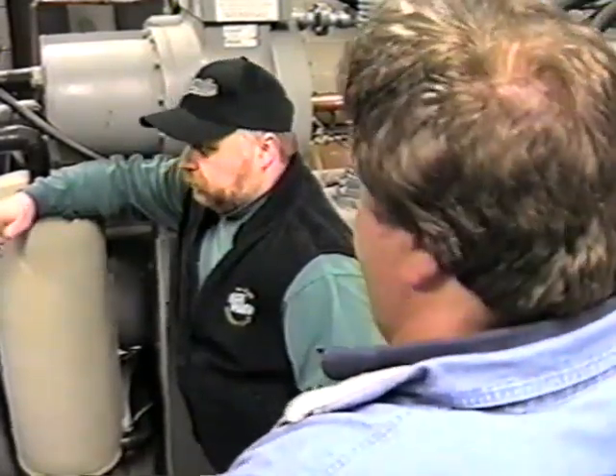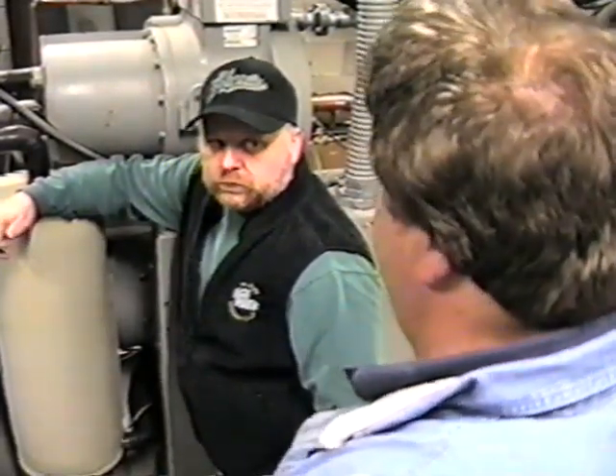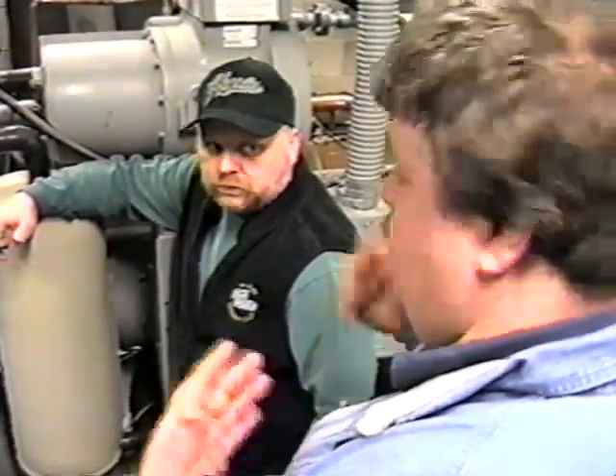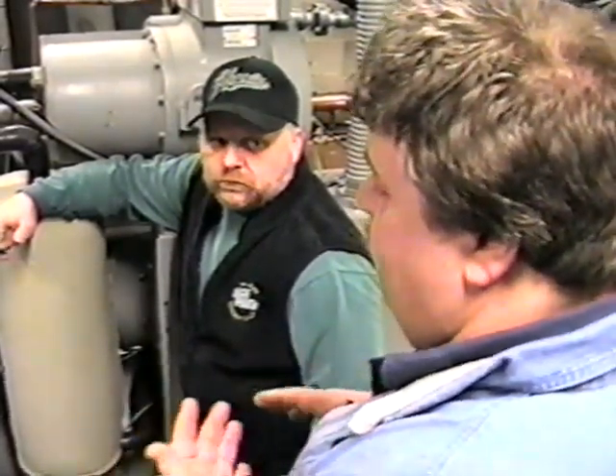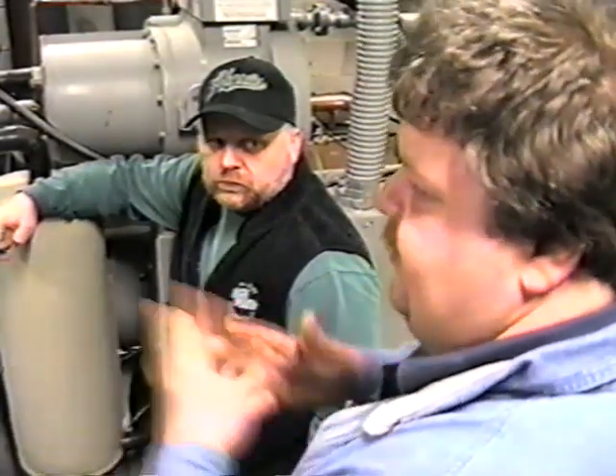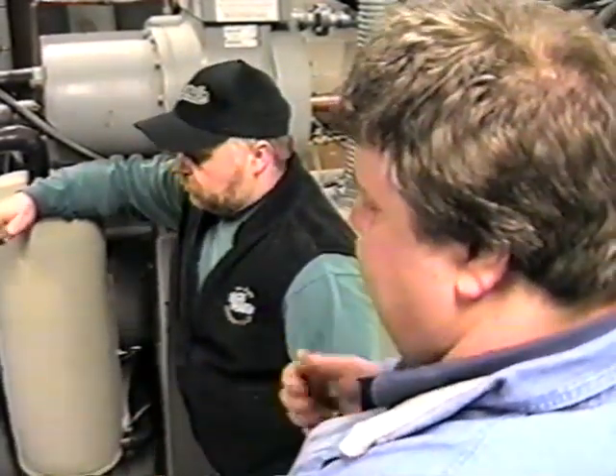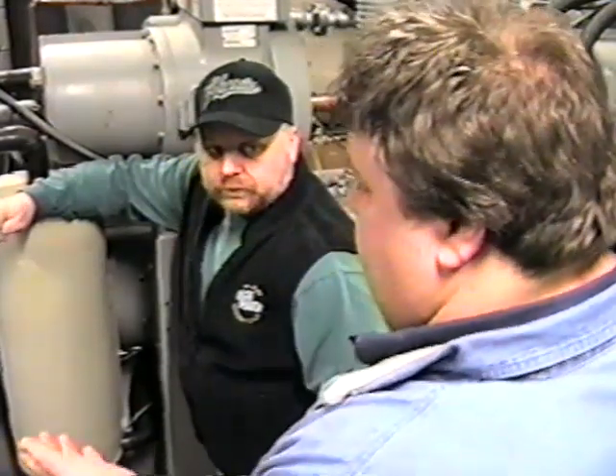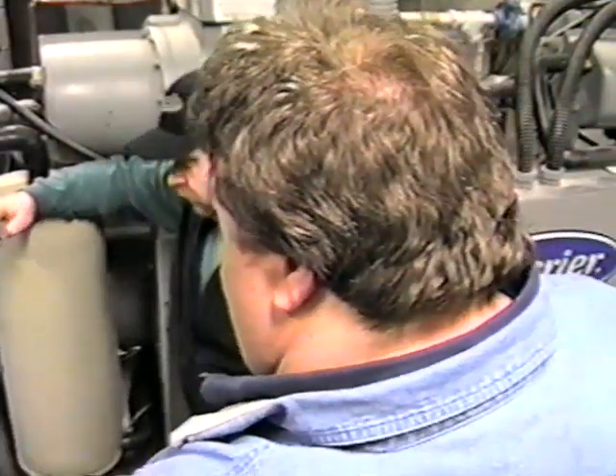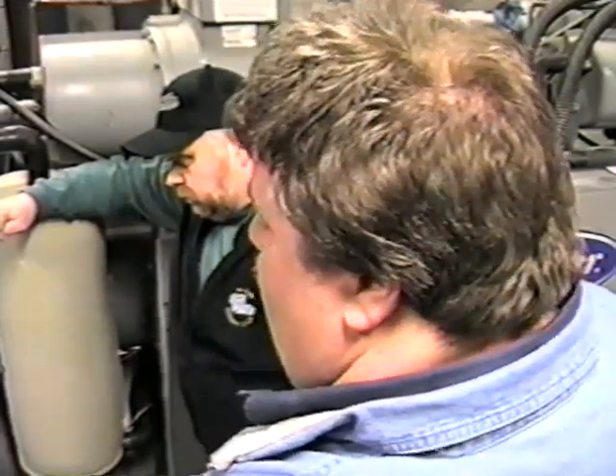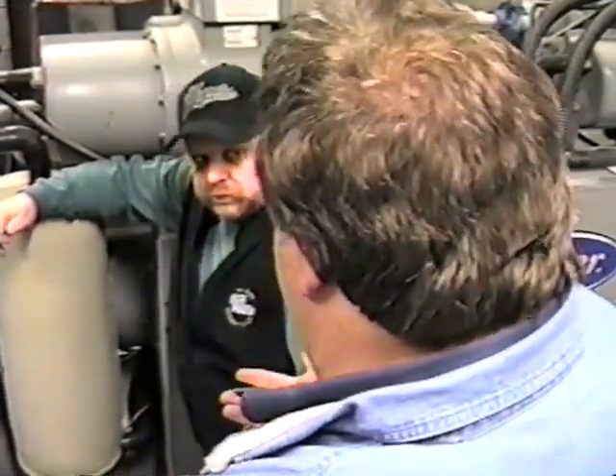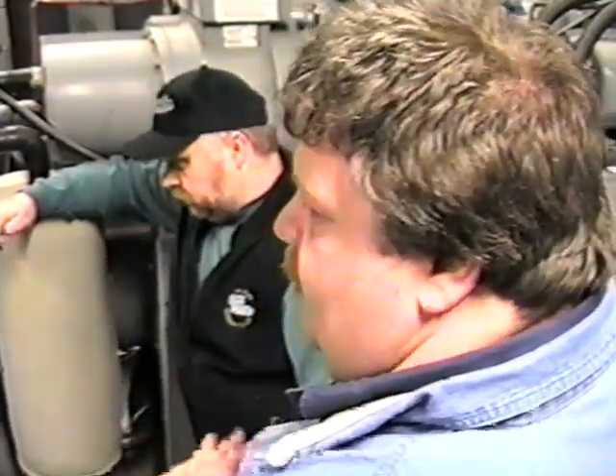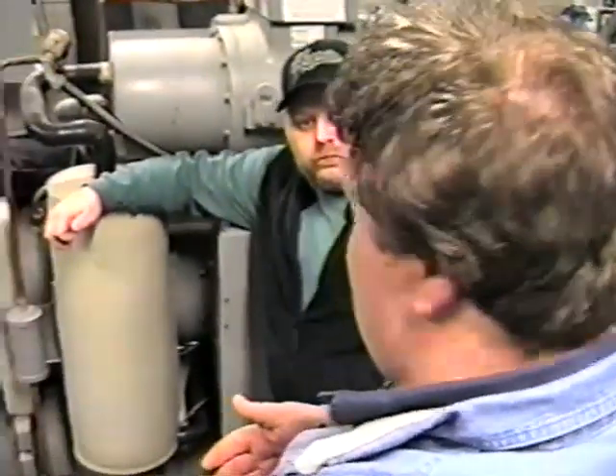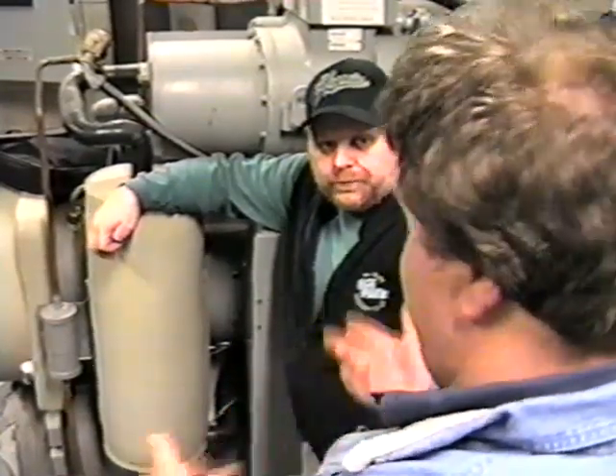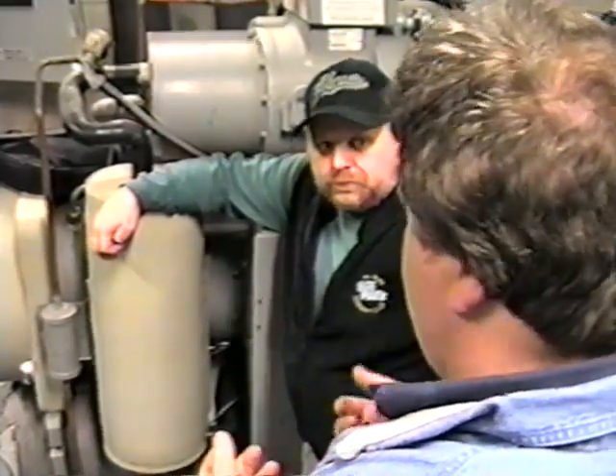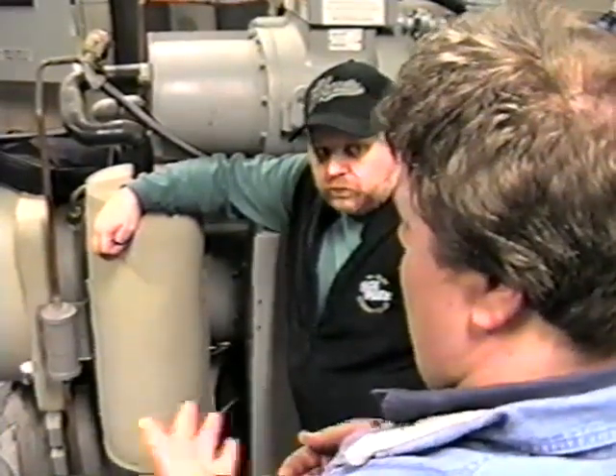So whatever we set it for, normally we set them down to the 15 degrees and let the chiller sequence up and do its own thing until we're satisfied with the ice temperature. Part of that running is that we're going to be monitoring also, while the chiller's on, the sump water temperature, which is our condenser water temperature. It's pretty critical. Like I say, we discussed before, we like to see it 70 degrees or above in order for the chiller to run reliably as far as the lubrication and that.